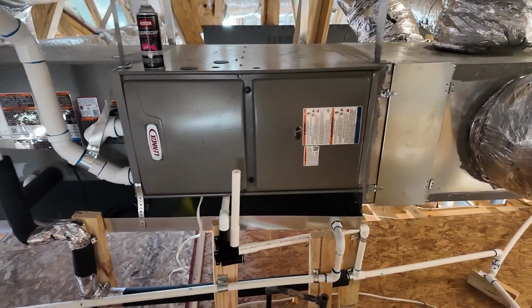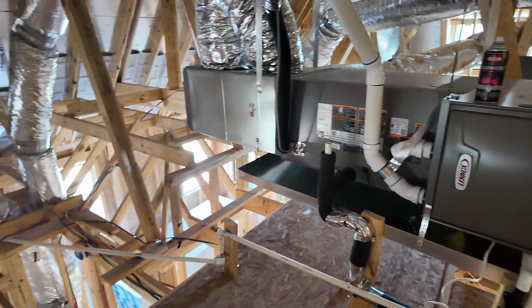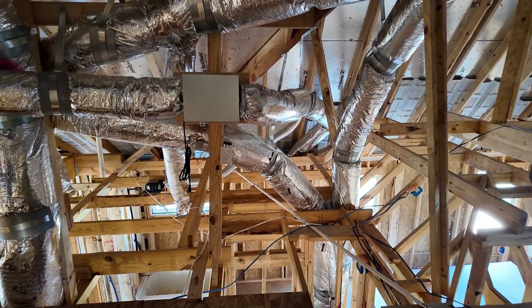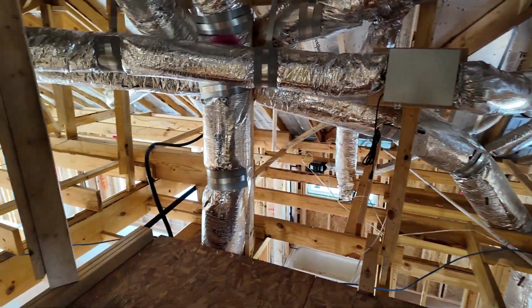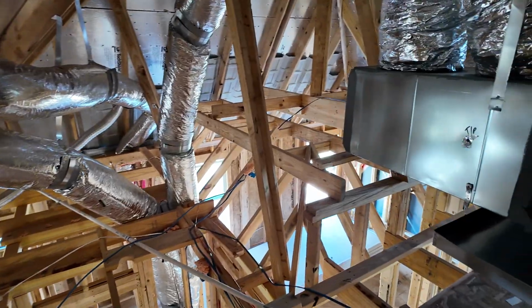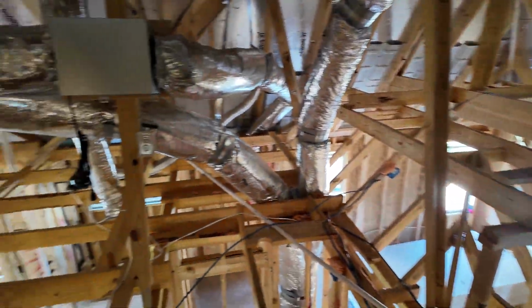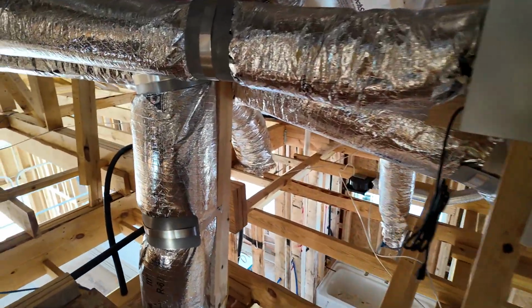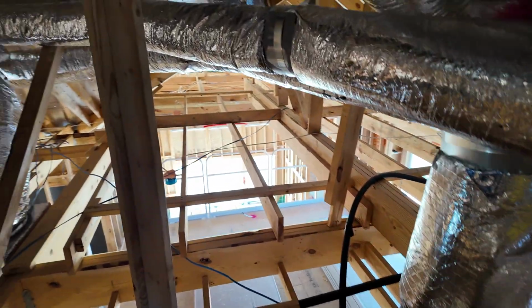Air duct shouldn't be touching other air duct. Air duct shouldn't be having some crazy bends. That's a crazy bend right there. Okay. I got any more crazy bends? Not too many more. We can help illustrate this issue. It's ongoing. It's some places I can't spray paint.